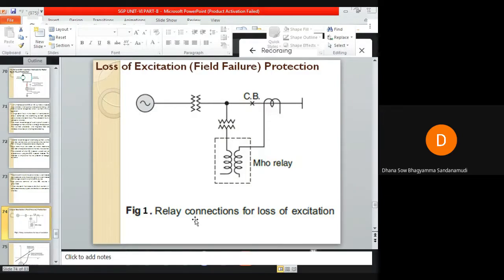Now, if the generator or alternator that I'm using is a large size machine, then large size machines cannot be allowed to run asynchronously for a longer period of time. A relative motion between the stator field and the rotor will induce large current in the rotor body, and therefore there is a higher rate of heating of the rotor surface. So if the machine is allowed to run asynchronously for a longer period of time, the rotor surface gets heated up, and a loss of excitation scheme can be used to trip the circuit during that condition.